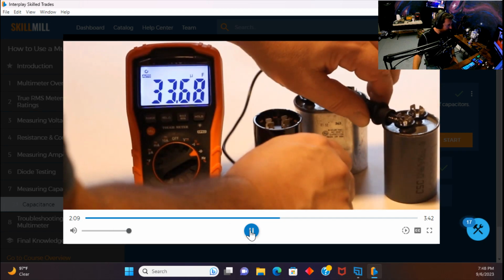Now the start capacitor is... Now that's one thing I did see earlier. Go off of what the capacitor says. Some capacitors say plus or minus 6%. Some capacitors say plus or minus 10%. It's going to have a higher microfarad value.